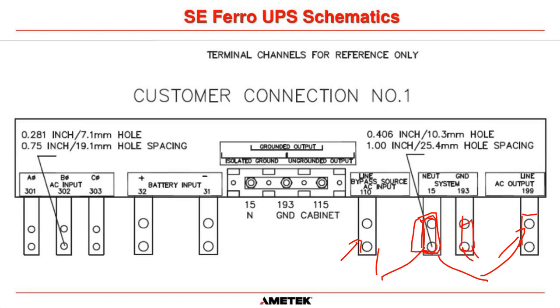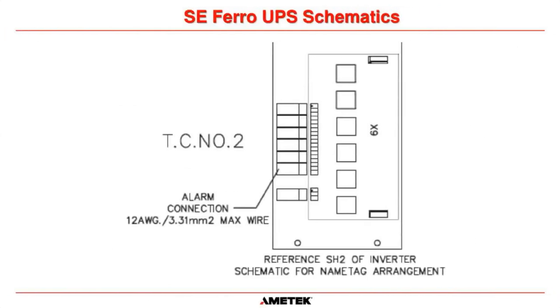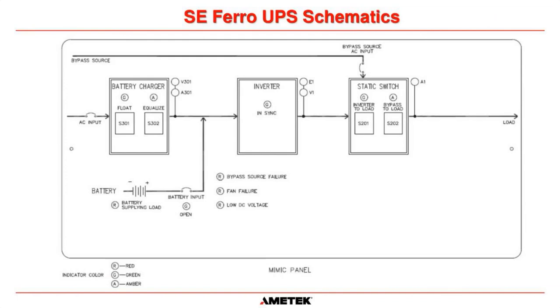We also have our alarm connections inside the UPS on the alarm relay board. It references sheet two of the inverter schematic for the name tag arrangement, which tells you which terminal is normally closed, common, and normally open, and gives information on how to connect your alarm terminations. The last part of the sheet drawing is the mimic panel, which is identical to what's on the front of the UPS.